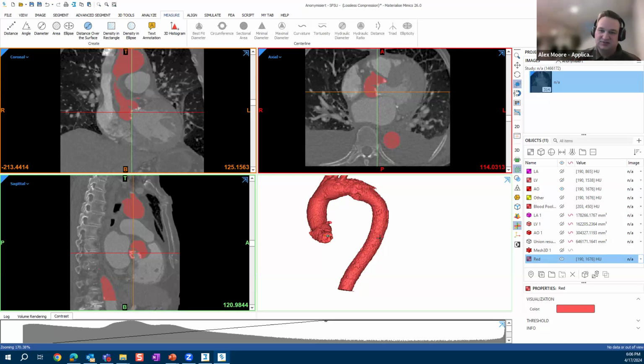So trained users can take their CT, their MRI, their 3D echo, use that medically cleared software, and if they're going to make a 3D printed model, we've gone through the process of validating the accuracy of certain printers and materials.